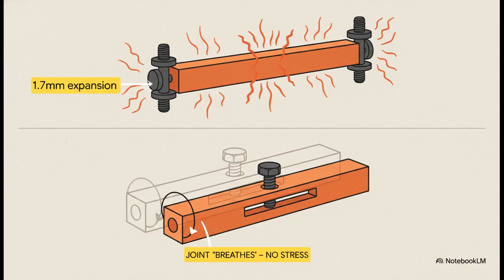And here's some cool physics in action for you. When all that current is flowing, the bus bar heats up, and metal expands when it gets hot, right? Well, a 1-meter copper bar will actually grow by 1.7 millimeters. If you don't account for that, the bar would literally destroy its own connections. The solution is so simple, but it's elegant. Just slotted holes. They let the whole connection kind of breathe.